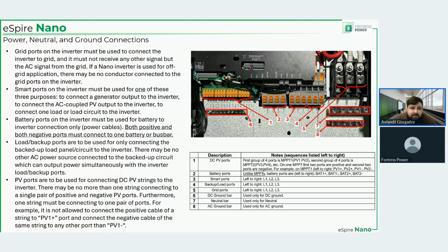Number 2 is the battery ports. There are 4 of them, 2 positives and 2 negatives. Although the way we want these ports to be used is that even if you have multiple batteries, do not connect one battery to one positive and negative pair and the other battery to another positive and negative pair. What we want to see is 2 cables coming from positive to one battery bus bar, 2 negatives coming to the other negative bus bar of the same battery. And then the battery itself has other batteries connected in parallel to it. So paralleling happens on the battery bus bar level, not the inverter port level.